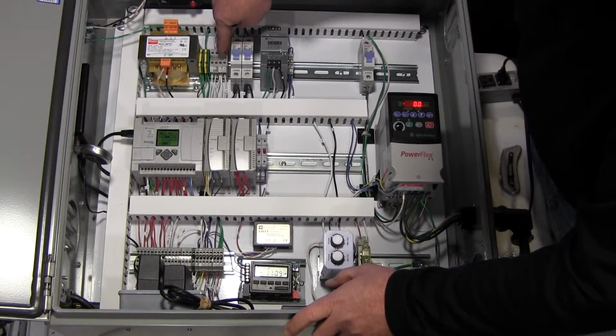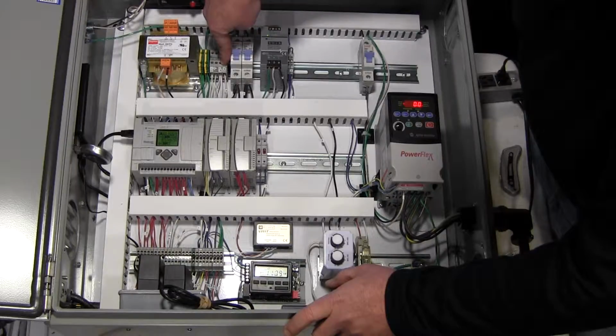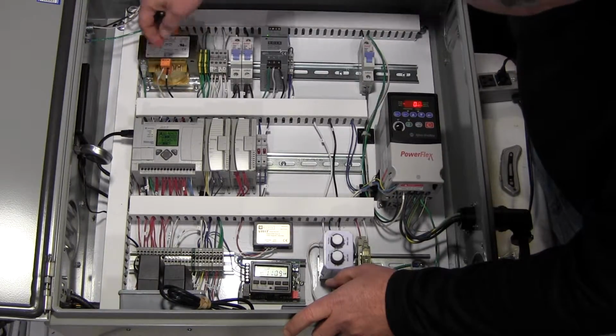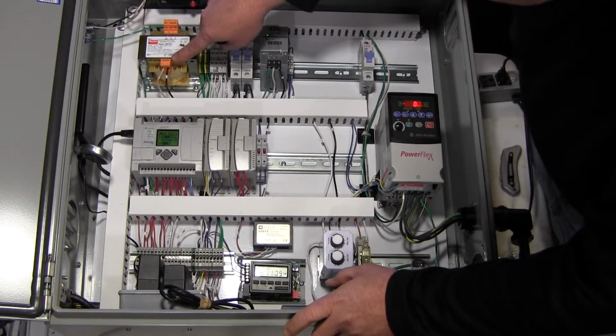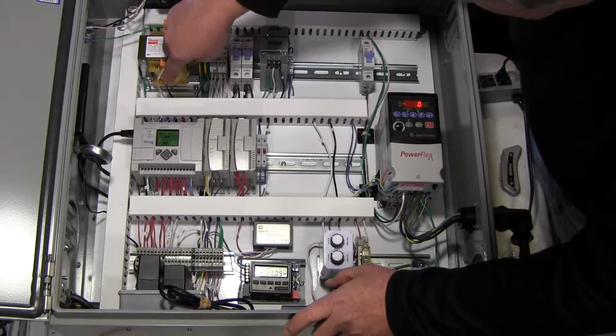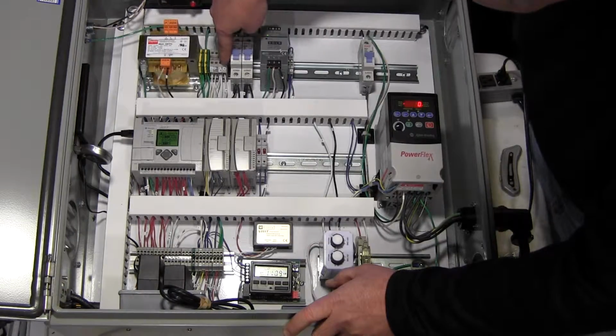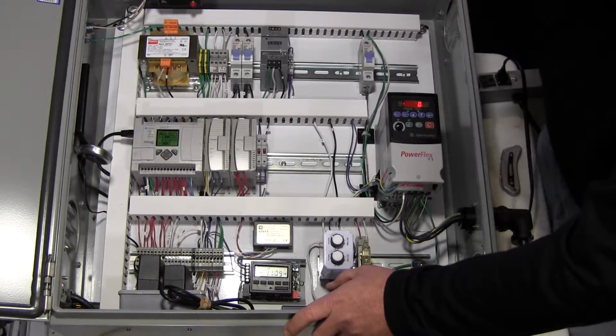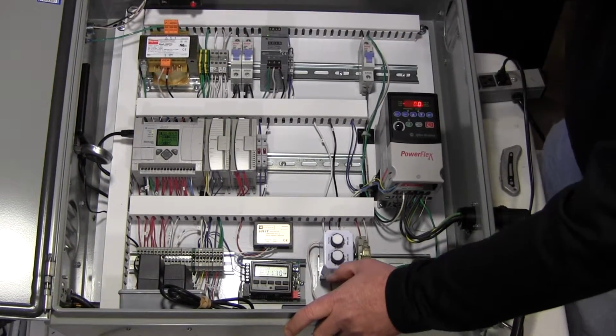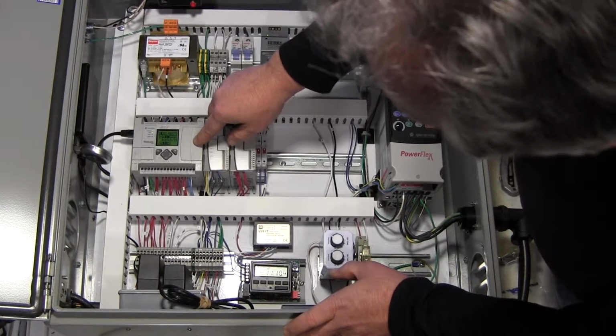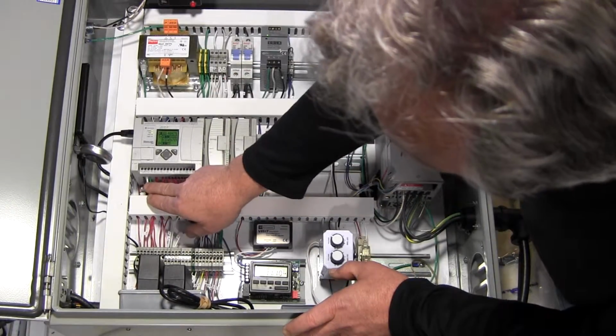This other one here, I talked about this before, this is the neutral to the 120 volts AC. If you take a look, there's a neutral here. This is the 120 volts into the transformer. It's got a plus and a neutral. The neutral actually comes back to this point right here. The controller itself, the microcontroller, gets its power from 120 volts.